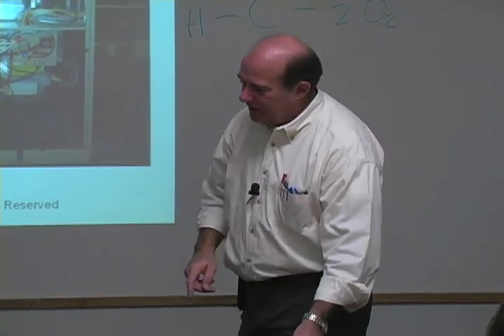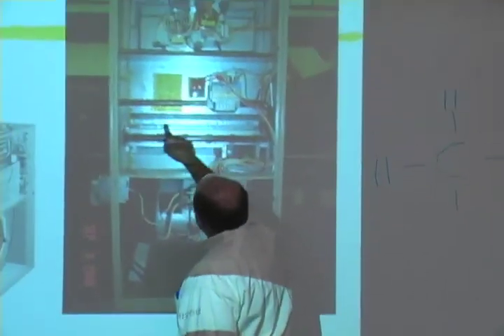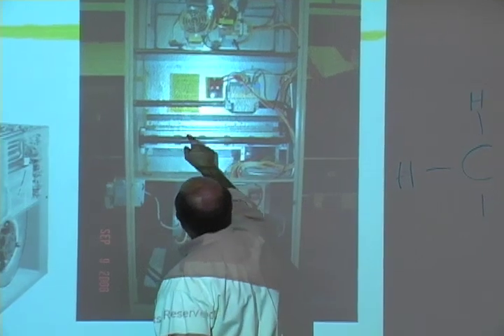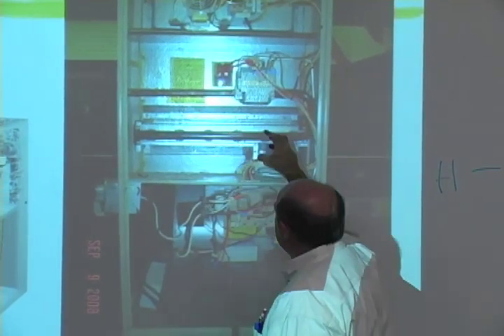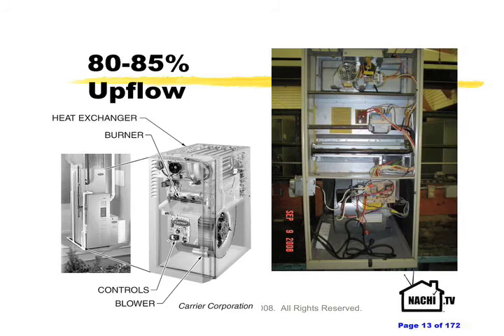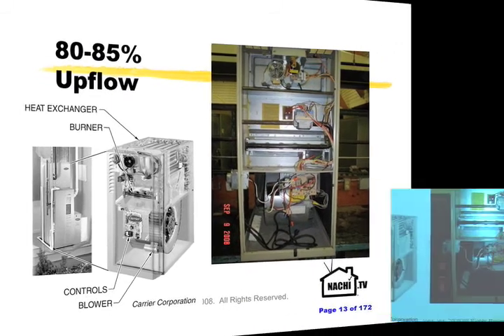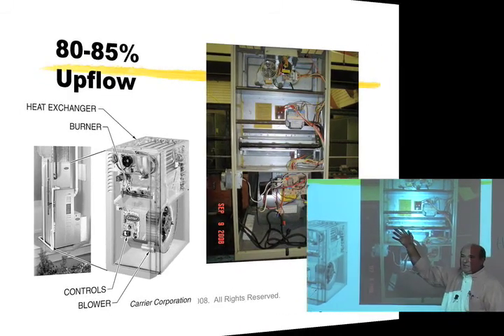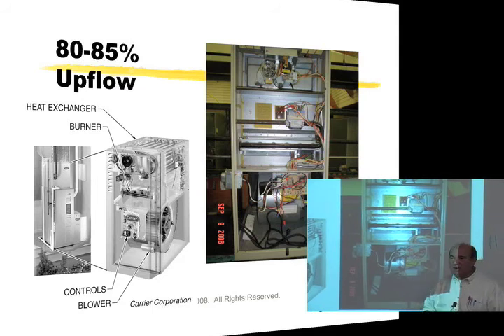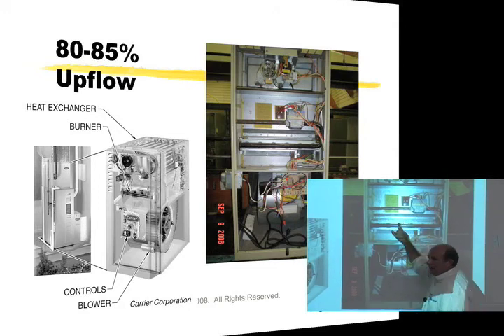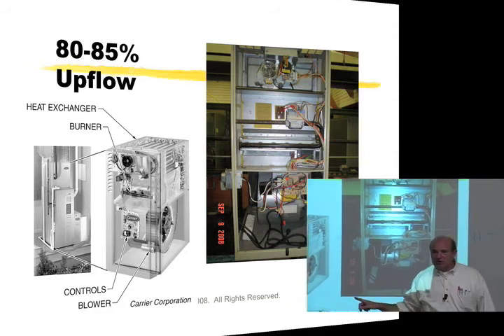We'll also see these little types of switches at different places along, maybe along the burner rack over here. So that if for some reason there's an obstruction or something in the system and it's not picked up by the pressure switch on the fan assist, and the flame starts backing up out of this furnace, it'll trip that switch as well. So we might have 2 or 3 or even 4 of these located at different places on the furnace. One over here, we may have one somewhere else on the lower part of the heat exchanger, one on the burner shield out here. That switch, we call it a rollout switch or a spill switch.